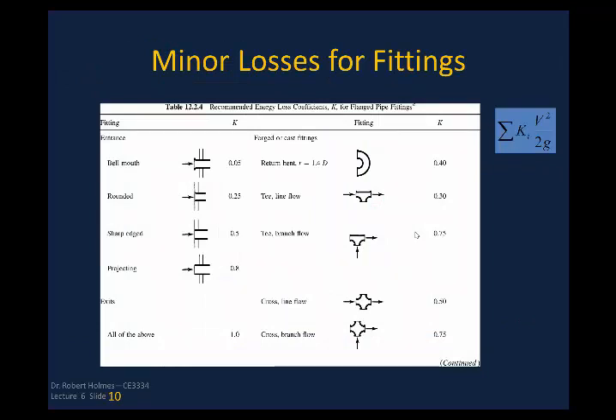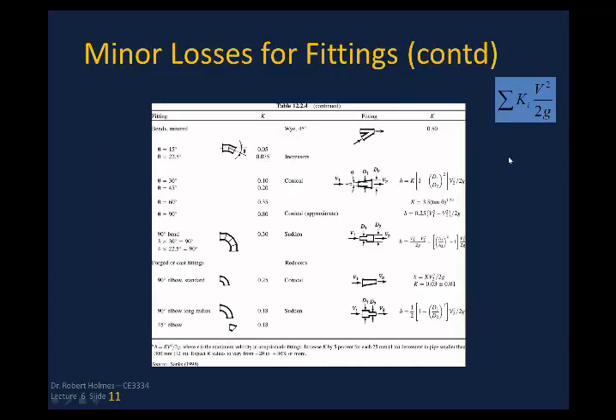For pipe fittings, valves, and things, these are some tables in your textbook. You can also look these up in design manuals. For like entrances of pipes, the bell mouth has a much smaller value of K because it allows for a gradual transition as opposed to a square-edged or a projecting pipe. Same thing with your fittings — you can see the values of K. The big thing here is the sum of those energy loss coefficients times the velocity head. Here are some more values for different types of fittings.